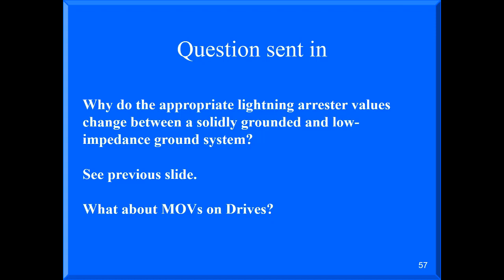You don't have UPSs? Minimal. What do you do to cover while the generator's starting? All cabinets have a battery backup unit on them. Oh, they're battery backups. Yeah, that makes sense. We only have UPSs on the network, also all servers. Can the people calling in hear the questions being asked here? I can repeat them for you. Okay. So the servers run at what voltage? AC or DC volt? We feed the busway at either 480 or 400. It all gets pushed down on the power supply at 48 volts.